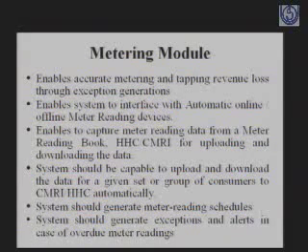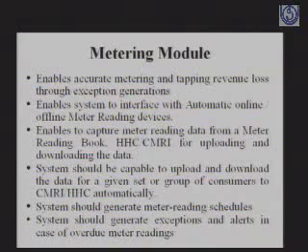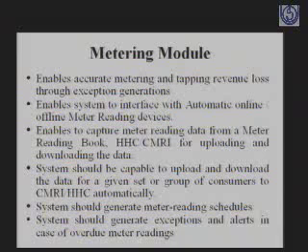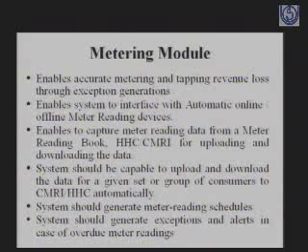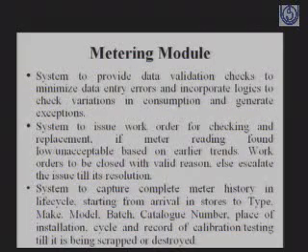Then the system also generates meter reading schedules, including the route map. If I have a GIS based system, as Mr. Rudra has expressed, I can read the maximum number of meters, or I can plan the route so that without wastage of time I can read the meters, number one. Secondly, I am also able to control that the distribution transformer meter is read on the same day with the set of consumers which are hooked to this distribution transformer, so that I get a proper energy balance. And the system will also enable me to generate alerts and exception reports.